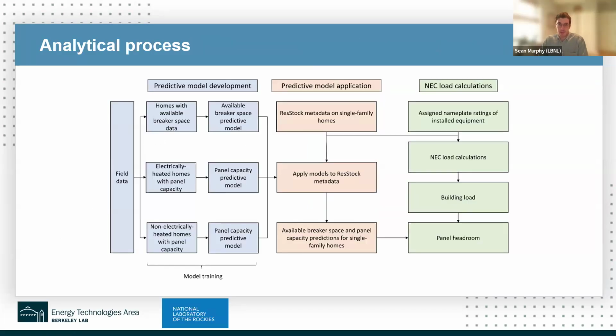So to summarize, we developed predictive models of panel capacity and available breaker space using field data on a range of housing characteristics. That's the process we show in the blue here. We then applied those models to a representative database of homes to estimate panel capacity and breaker space nationwide. That's the orange section of the diagram. Then we simulated the NEC load calculations using data from ResStock, and for each home, compared panel capacity to the load calculations to determine the amount of headroom, the remaining capacity in those panels to serve new loads. And that's the green section of the diagram.